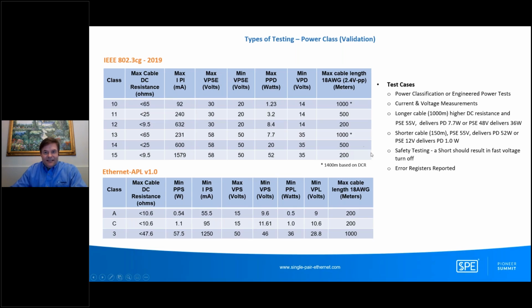So when we test this too, we have to make sure that since we're delivering voltage and current, if somebody were to short the twisted pair cable, the differential pair together, it should result in a fast voltage turnoff. So if you short the positive and the minus conductors, you should turn the power off within 75 milliseconds. So there is some safety testing that goes on to test this, as well as error registers should be reported from the device if there's power faults. And there's a whole mix of testing going on too, with the slew rates and over current limits and under voltage current limits, and all of this is defined in the standard, but it's really so much detail that it's too much to discuss in today's talk.